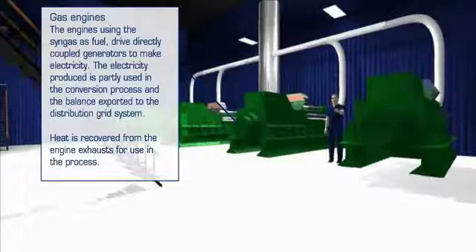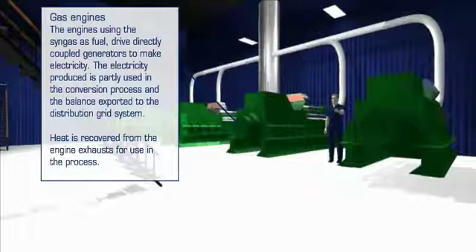Energy is recovered from the engine exhausts and is converted to steam. This steam is combined with the steam produced from the syngas cooling system and is used either to provide additional power generation or for export as processed steam or hot water — for example, to a district heating system. Finally, engine exhausts are combined into a single, low impact stack for discharge, with the final engine exhaust meeting all European and national emission standards.